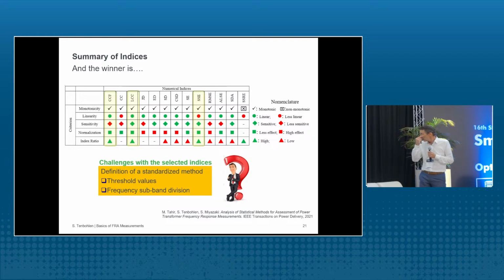And so we investigated these values based on a database which was collected by Cigre. We had there 140 FRA measurements of different transformers, with different mechanical deformations, and checked which indices are good. In this case it was CCF, LCC, and SSE. Keep that in mind, maybe not that important, but most of these proposals are not good for an objective interpretation, because they have to be monotonic, linear, sensitive. There are different parameters which you can test for these indices.